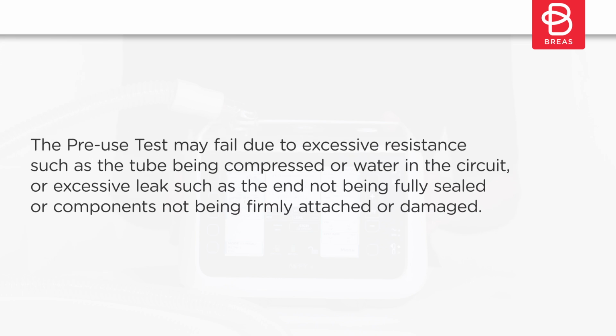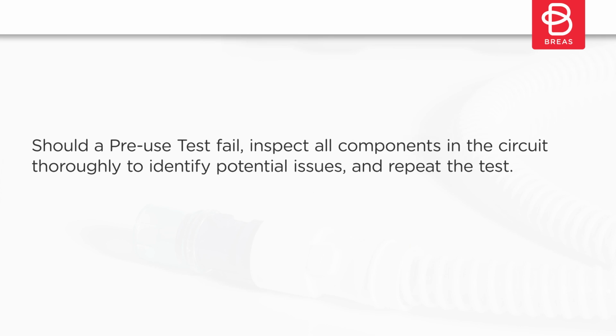The pre-use test may fail due to excessive resistance, such as the tube being compressed or water in the circuit, or excessive leak, such as the end not being fully sealed or components not being firmly attached or damaged. Should a pre-use test fail, inspect all components in the circuit thoroughly to identify potential issues and repeat the test.